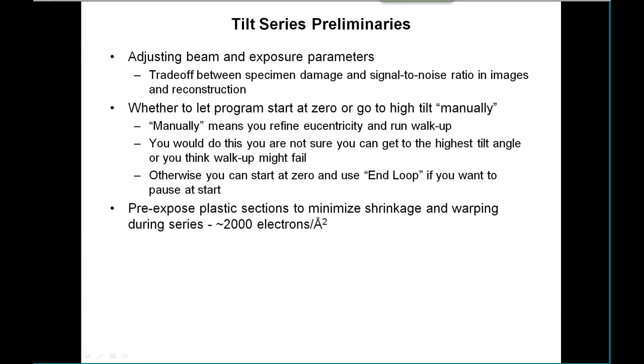Before you get into taking a tilt series, the main points are that you need to adjust the beam and your exposure parameters. This is a difficult thing in all situations because there's a perennial trade-off between the specimen damage and the signal-to-noise ratio in images and in the resulting reconstruction.